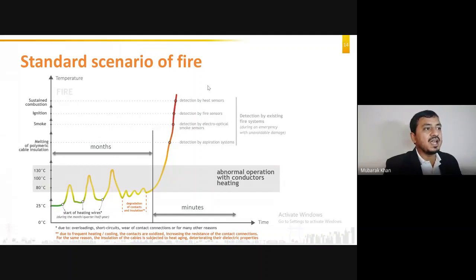Under these scenarios, your existing fire detection systems will work. You have a smoke sensor, fire sensor, or even the fire suppression system, which are being installed in some of the panels. They will only work after the fire has already occurred and damaged some of the equipment, right? So this is a standard fire scenario, how it happens. We will revisit this slide further in future, but just to understand how the fire occurs, we have seen this. Now our focus is through thermography or other techniques. Our focus is to monitor and mitigate the issues within this range, within the safe zone of 80, 100 and 130, so that we eliminate the effects of fire.